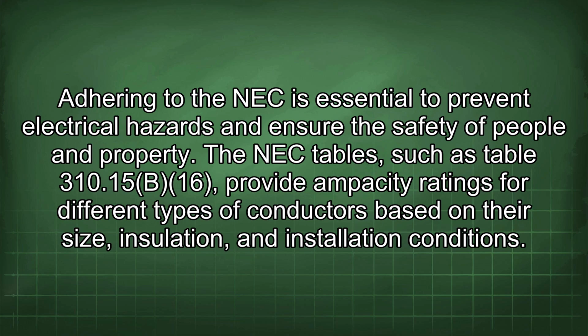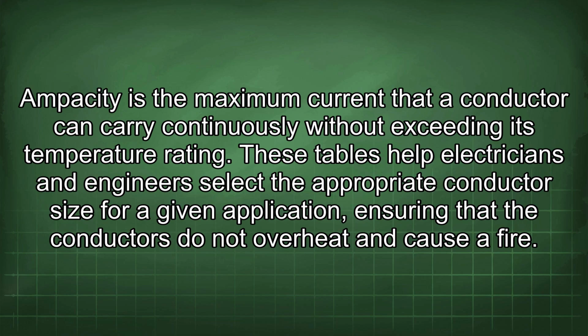The NEC tables, such as Table 310.15b16, provide ampacity ratings for different types of conductors based on their size, insulation, and installation conditions. Ampacity is the maximum current that a conductor can carry continuously without exceeding its temperature rating. These tables help electricians and engineers select the appropriate conductor size for a given application, ensuring that the conductors do not overheat and cause a fire.